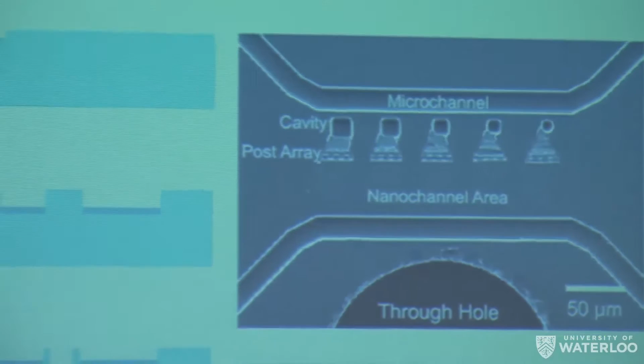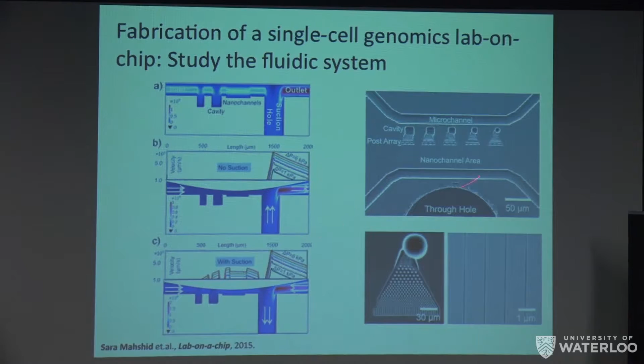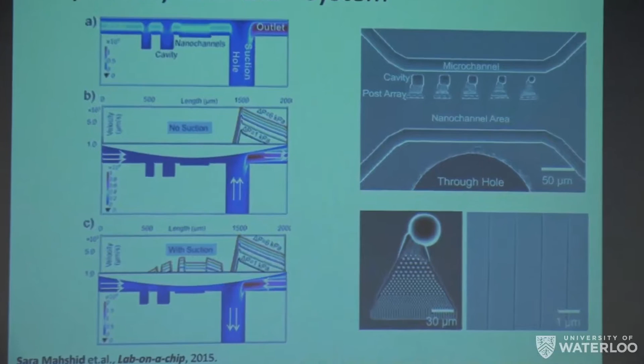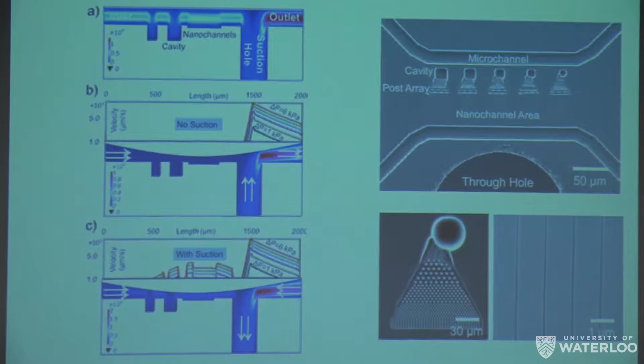That's why we need to overcome this problem by having a suction through hole close to the confinement system. Here, when the lid is all the way down, we have a very high resistance, and we cannot easily actuate flow for cell lysis and other buffer exchange for other biological exchange. That's why we design a suction through hole close to the confinement area, and by applying a negative pressure, we can bring enough solution into the device and initiate the lysis.